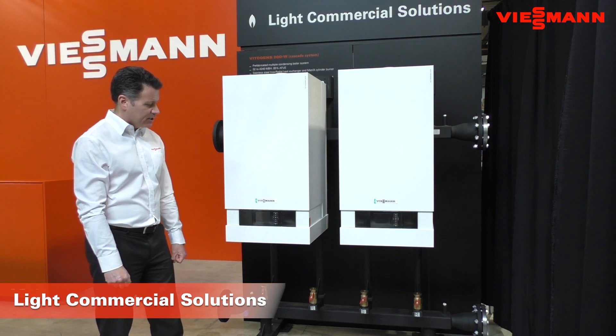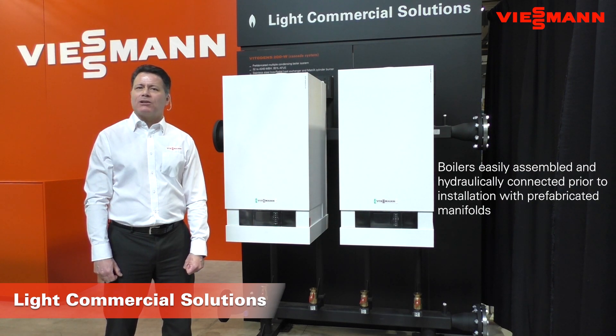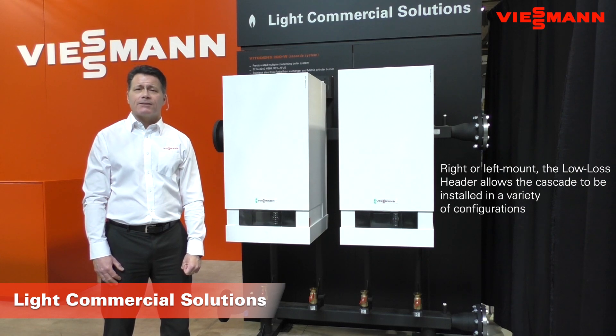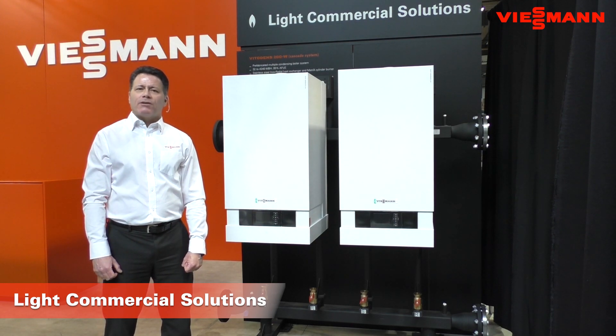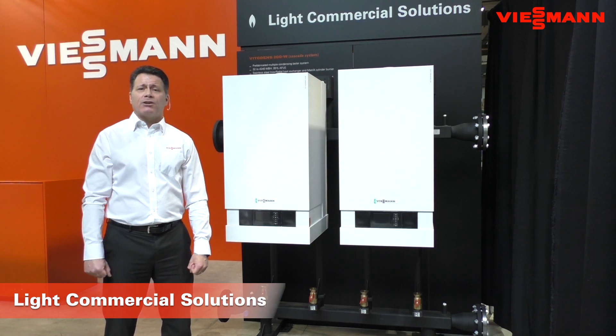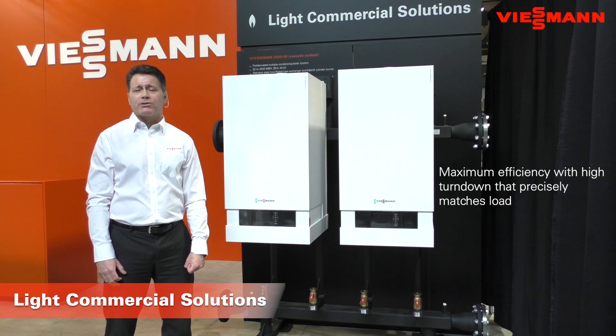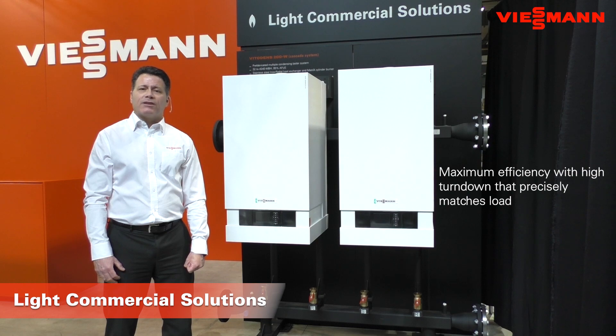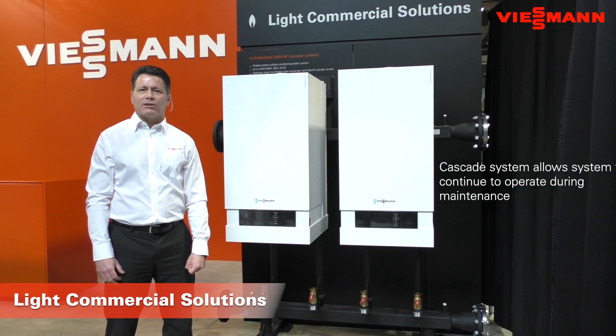The next point is the clean lines and uniform product you get once it's assembled. All of the boilers are plumbed through, with all piping including pump connections below being neat and tidy, leaving only your field connection supply and return on either end. The fourth point is turndown — there's a tremendous turndown ratio. You're operating from a single boiler on low fire up to all boilers at 100% input. For an 8-boiler system, that's a firing range from roughly 100,000 BTUs up to over 4 million BTUs on high fire, which also provides inherent redundancy — should one boiler go offline for service, the others will continue to operate with little or no disruption to the building.